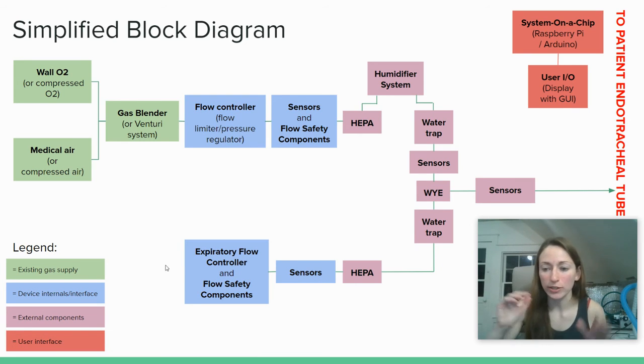So regardless of what choice of solenoid valves and proportional valves or mass flow controllers you use for these control components, most designs sort of boil down to this fundamental block diagram. You may also have extra takeoffs for emergency breathing valves to enable the patient to breathe in the event that all the valves get locked closed, but it sort of boils down to this.